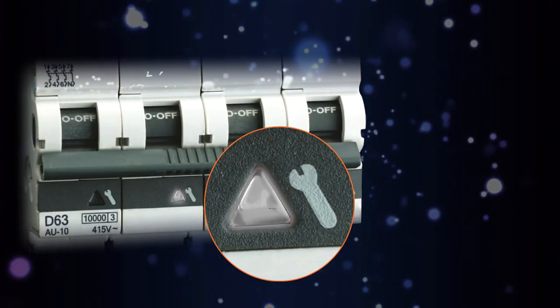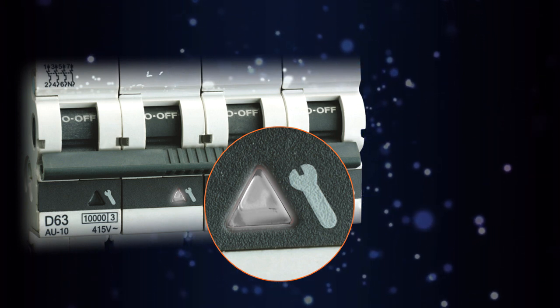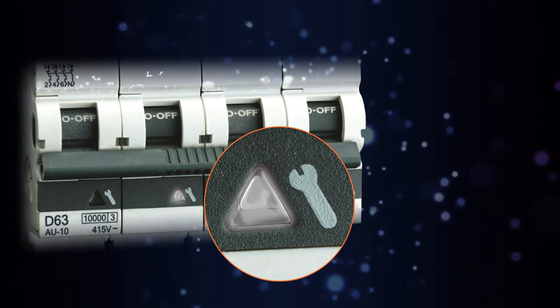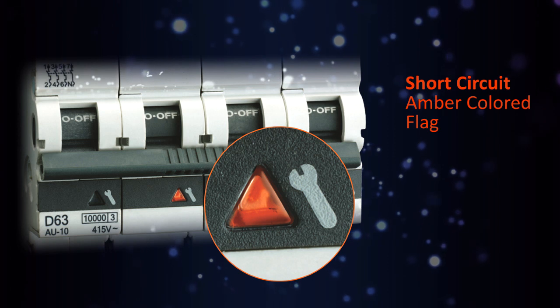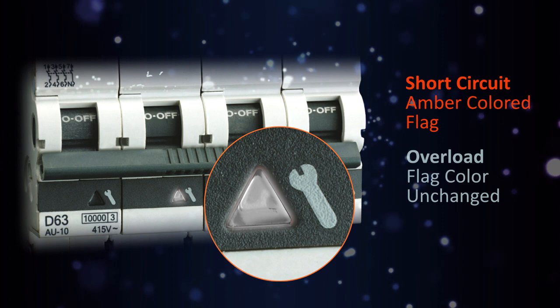Is there any means by which one can know the reason for MCB tripping? The answer is yes, with our AU range of MCBs. When these MCBs trip on a short circuit fault, it indicates through an amber-coloured flag, and there will not be any indication when MCBs trip due to an overload fault.